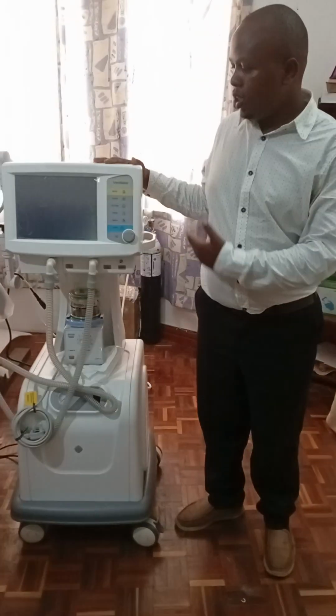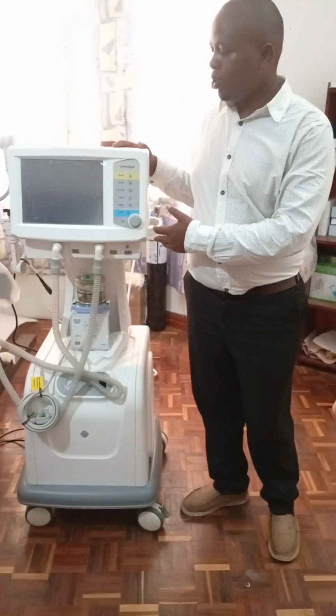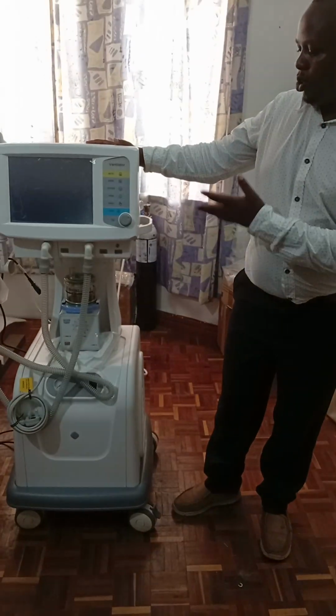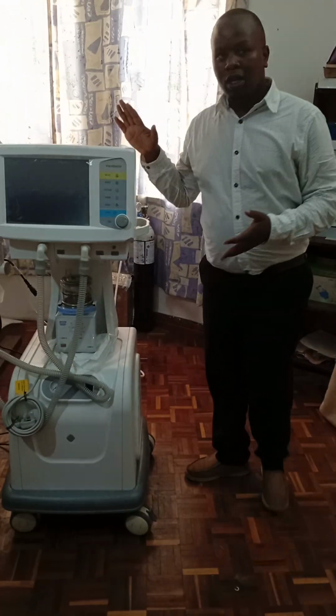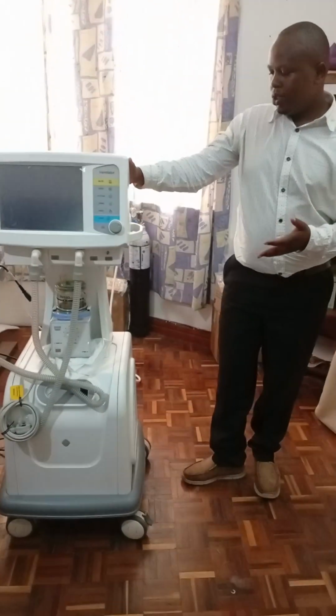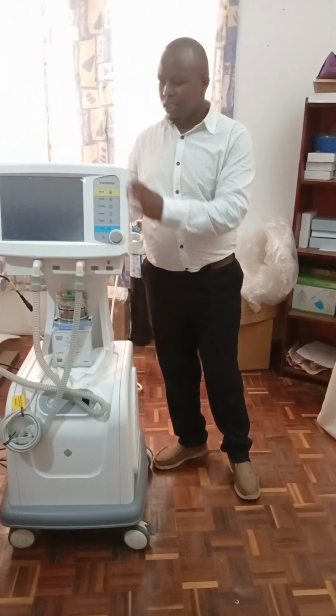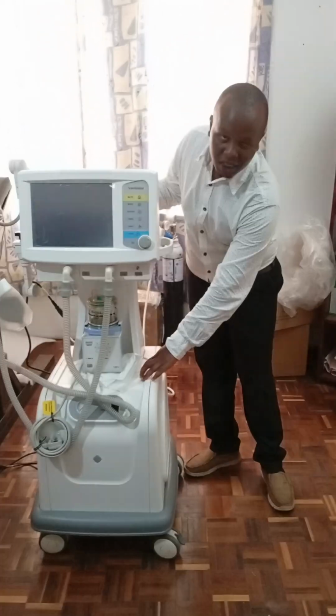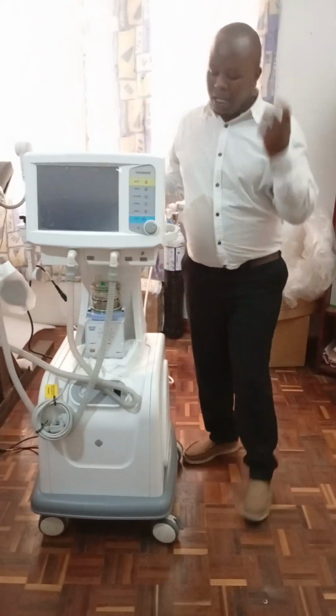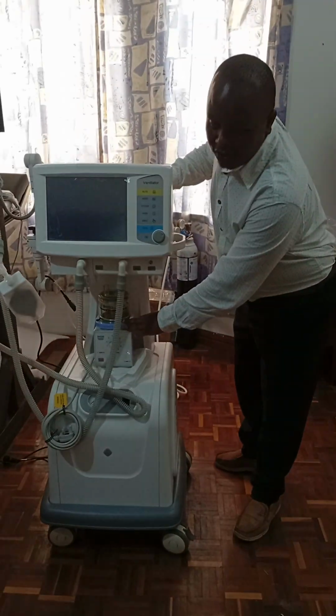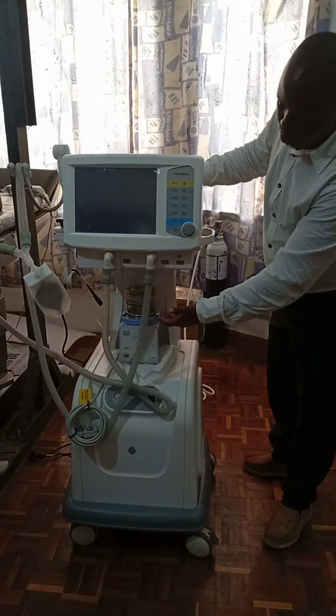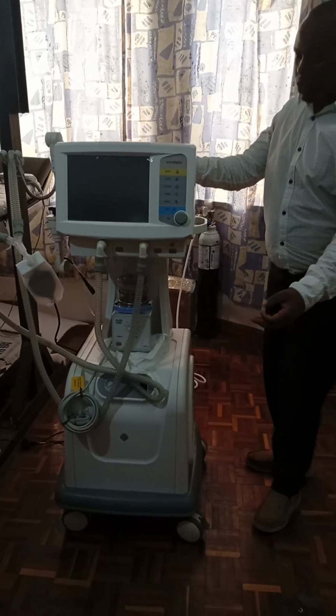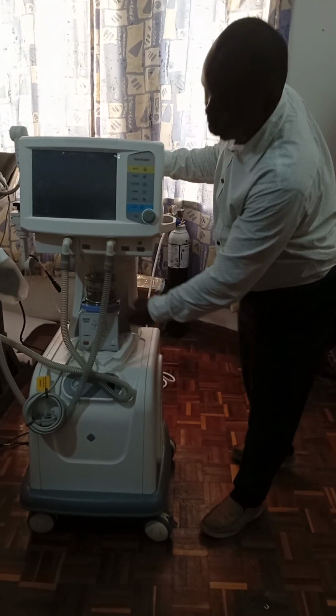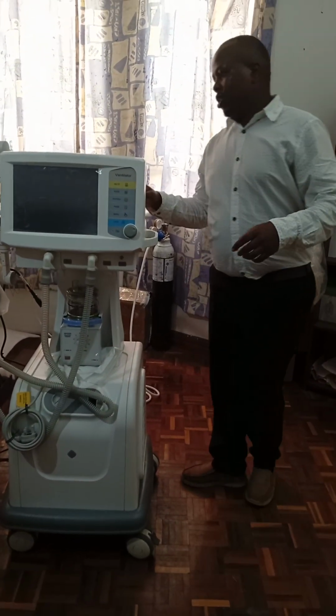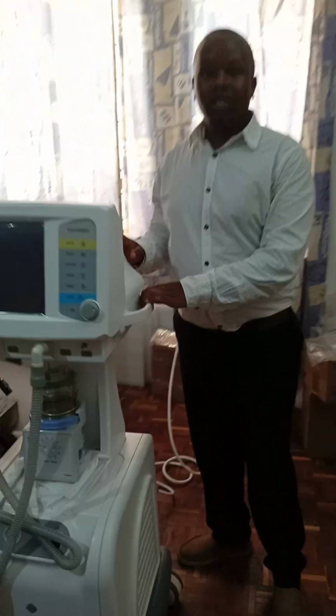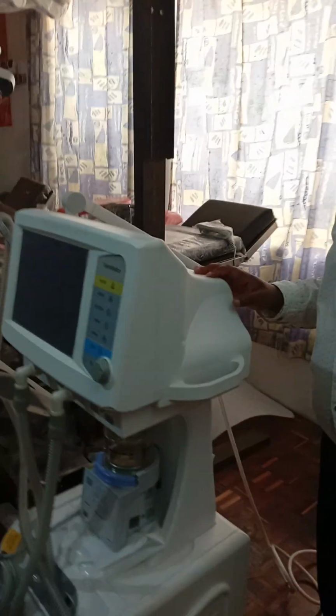Normally, before we go into the details on the operation, I'm just going to show you the topography of the machine. This upper part is the ventilator, and this lower part is a compressor. In the middle, we have the humidifier to help us not give the patient dry air. You'll be putting in distilled water so that the air the patient is breathing is moist.